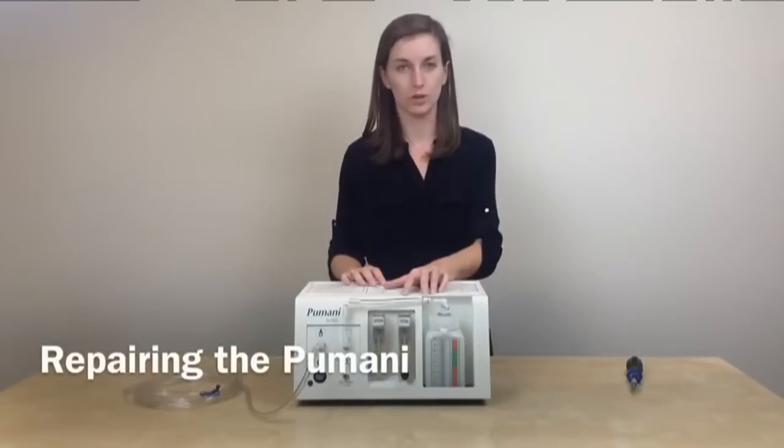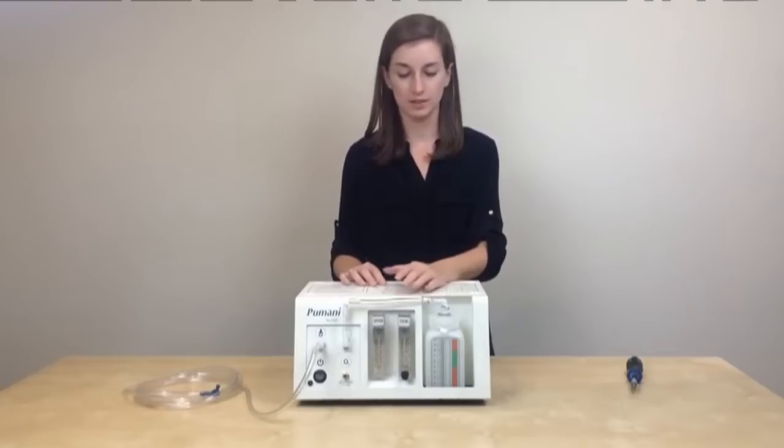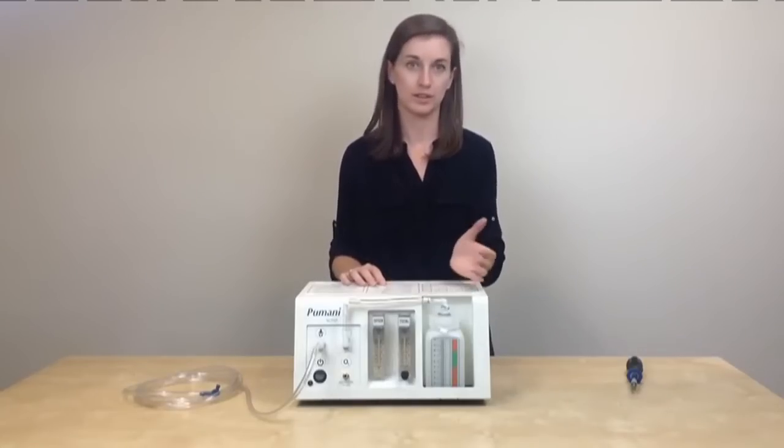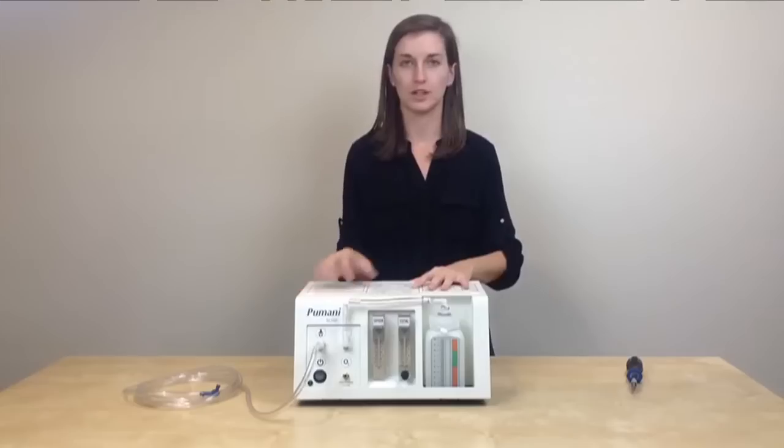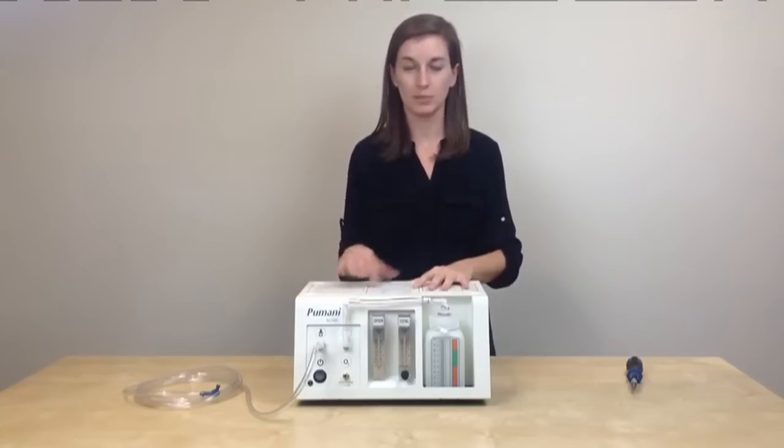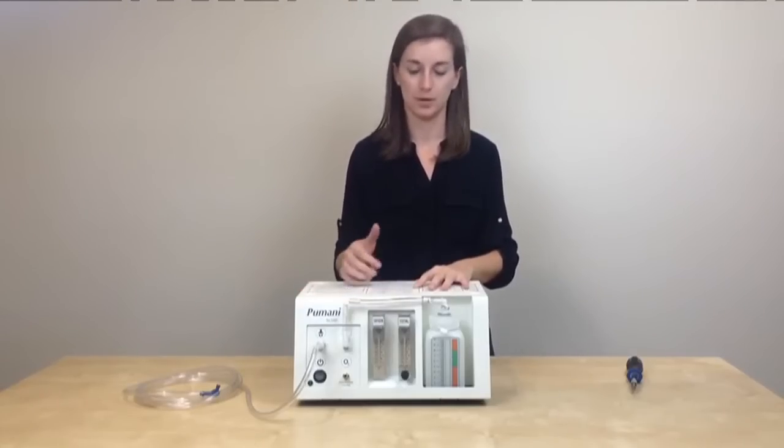If you notice that the total flow out of the Pumani is lower than it should be, so lower than 10 liters per minute, you may need to open up the unit to check for any loose connections, and you may need to replace the filter under the pump.